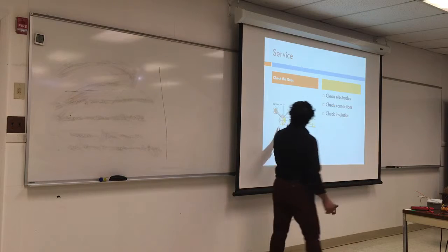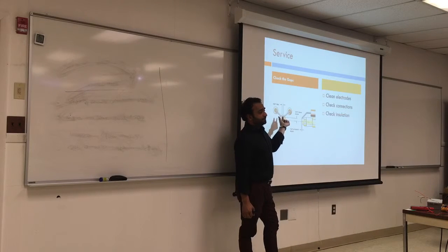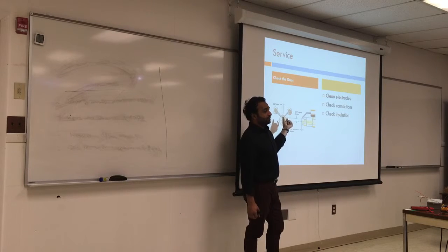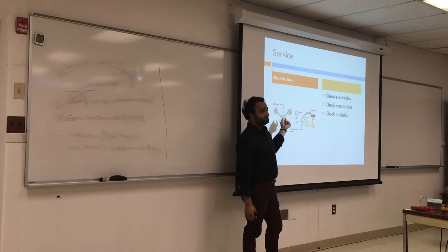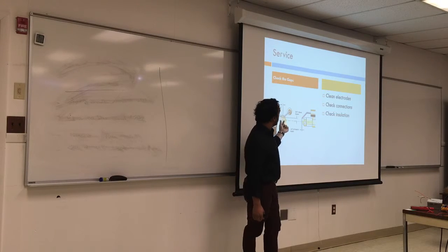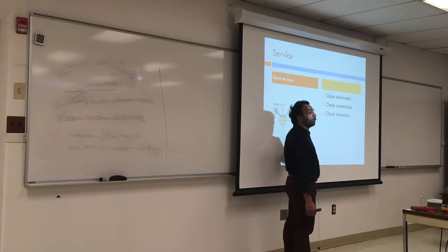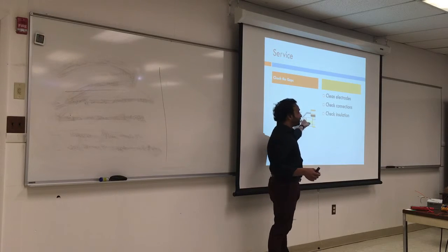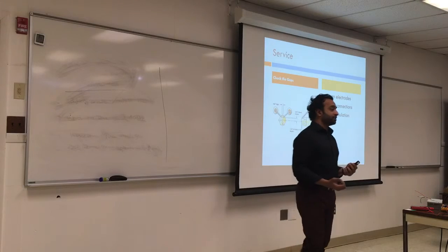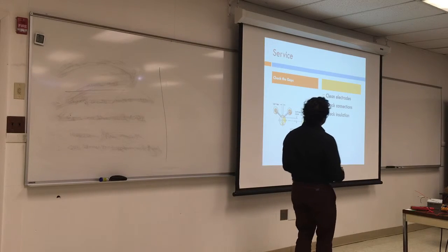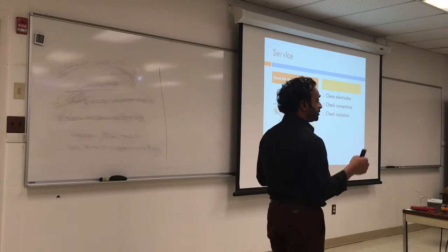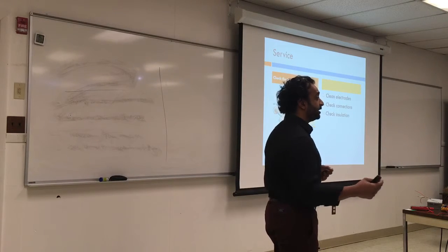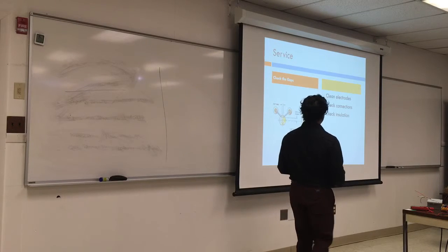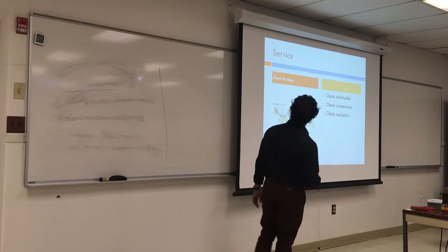The gaps. The gap here is specific to each burner, it should be according to the manufacturer. When in doubt, if there is no guide, we're going to use 1/8 of an inch as the general rule for this gap. And the gap has to be the right distance from the nozzle. You don't want it to arc to the nozzle, because any arcing happening before those tips meet will reduce the voltage coming into the electrodes. So you want to have clean electrodes, make sure the tips are matching. If one of them is worn out, you have to replace both of them. Check the connections and check the insulation getting all the way to the electrodes.